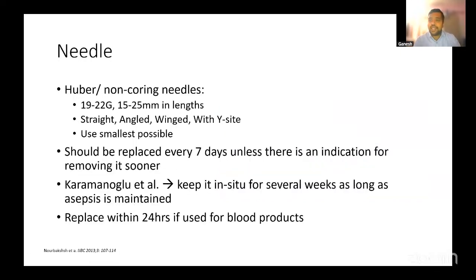There are various lengths and diameters of non-coring needles available. They can be from 19 to 22 gauge, and 15 to 25 millimeters in length. They can be straight or angled or winged or with a Y-site. The basic idea is to use the smallest possible, because the smaller you use, the less damage it will cause to the septum, and the longer the life of the port is going to be.